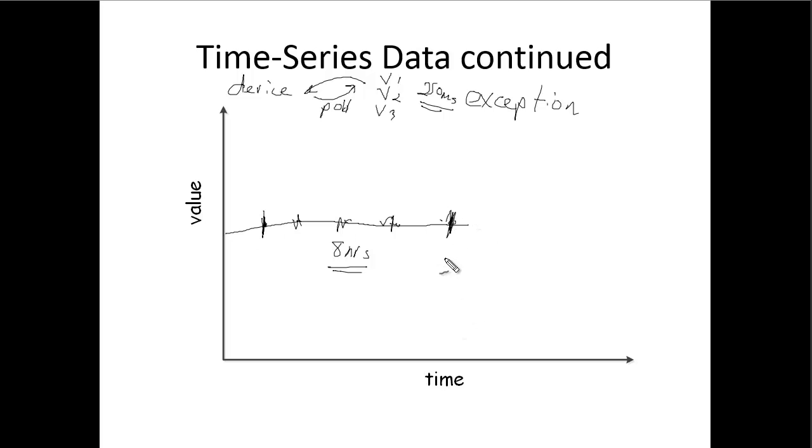that I've got a problem with my system, but I'm throwing those out, and then when this starts happening, all of a sudden, well, these values are all different, right? So I'm going to save every one of those. So right here, I'm going to have more readings. Okay, so right there, I've already improved my situation, because when nothing interesting's happening, I'm not taking a whole lot of information. When something interesting happens, well, now I'm taking more readings, right? So this right here, this doing exception compression compresses my values, right?